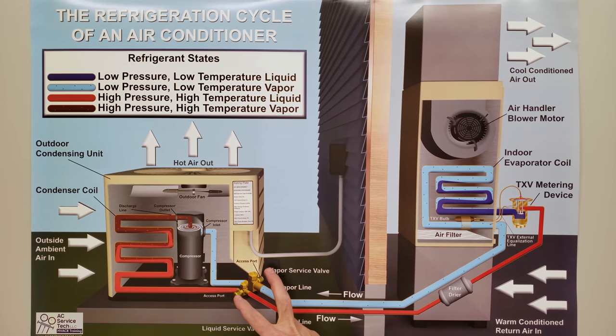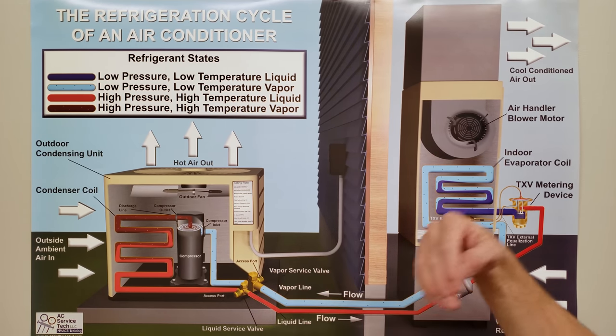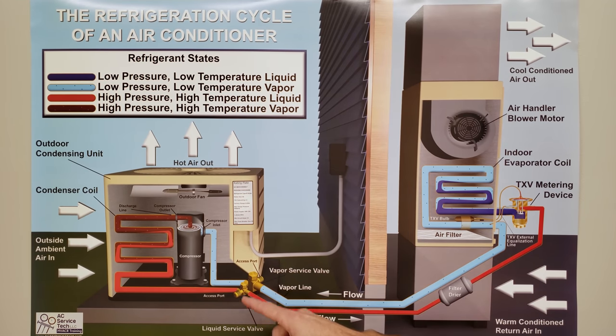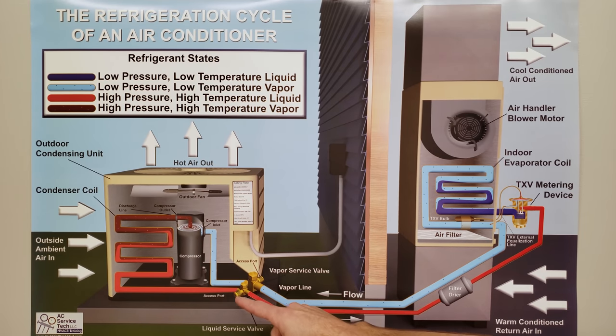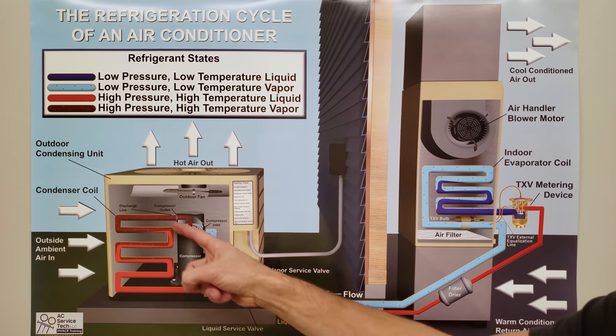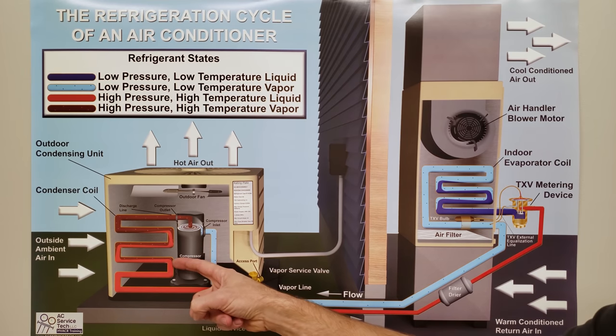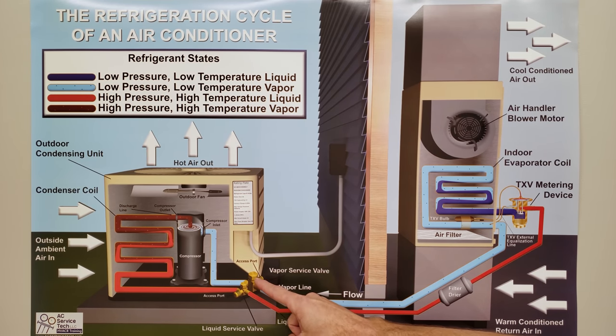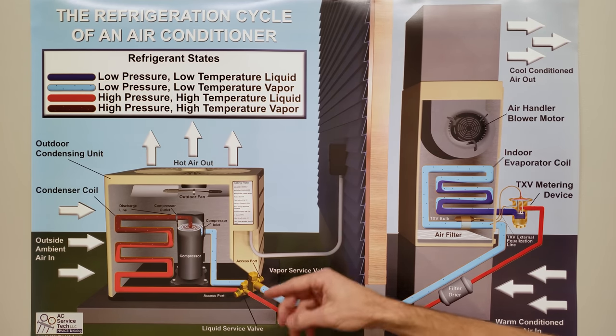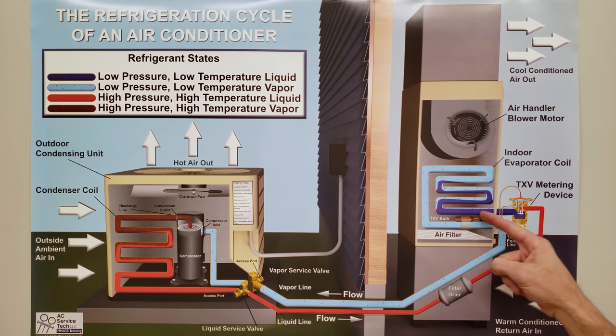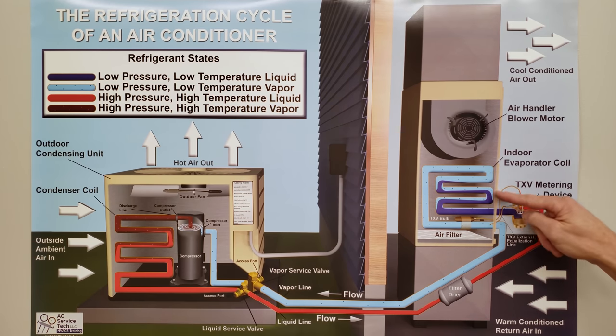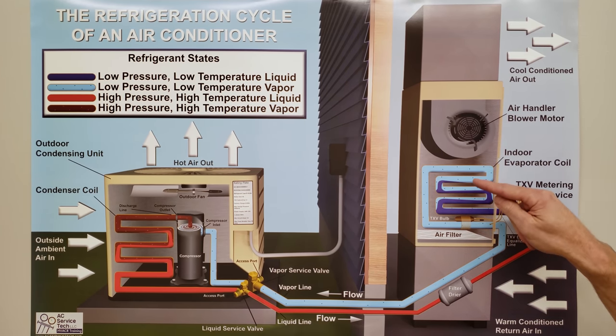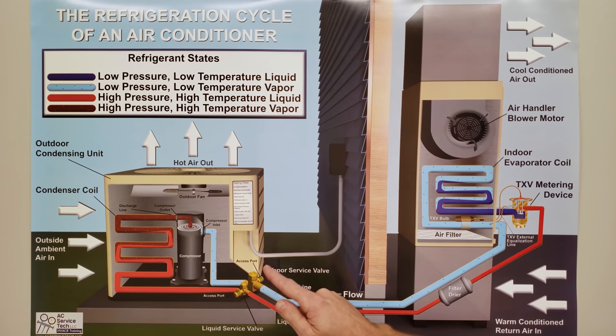When we check the pressure of a system, we're not just checking pressure by itself — we convert it to temperature because the whole system operates on temperature. Checking the pressure on the vapor line and converting it to saturated temperature lets us determine what temperature the refrigerant is at during the phase change inside the coil, even though we're measuring far away from it at the vapor port. We use that to determine total superheat and subcooling.